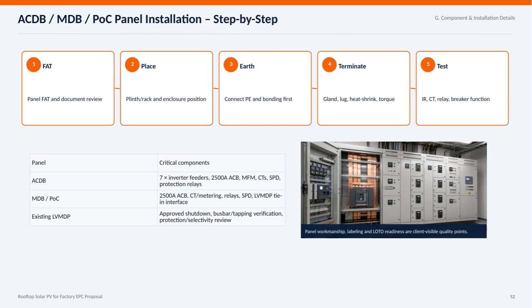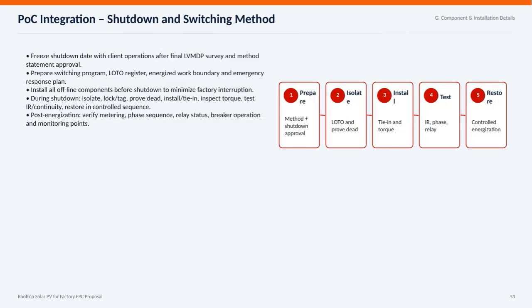First, we start by finalizing the shutdown date in coordination with the client's operations, but only after completing the LVMDP survey and getting the method statement approved. Then, we prepare a detailed switching program that includes the lockout-tagout register, defining the energized work boundary, and setting up an emergency response plan. To keep disruptions minimal, all offline components are installed prior to the actual shutdown. During the shutdown itself, we carefully follow a sequence.